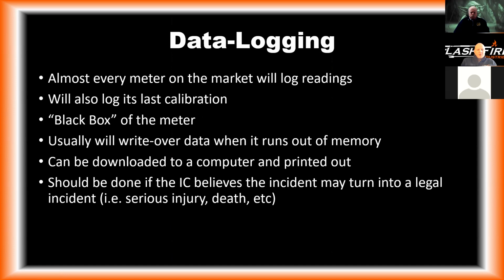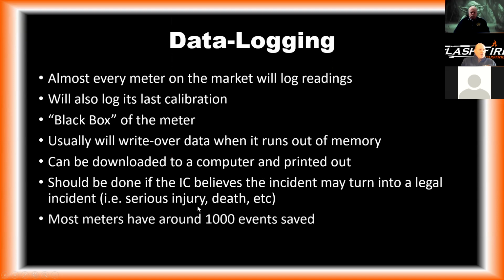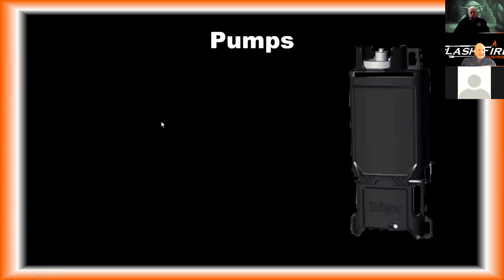So if you go to a high profile incident, and I consider high profile like death or close to death or something that you think might be litigated down the line, then this could be downloaded to your computer and saved as a copy, a record for the lawyers, PD, whatever the case may be. Usually about 1,000 events, and most meters will take a record every 30 seconds to a minute. So just be aware it's there. You go to a high profile event, we can download those readings and save them for future litigation, because that's the world we live in now.